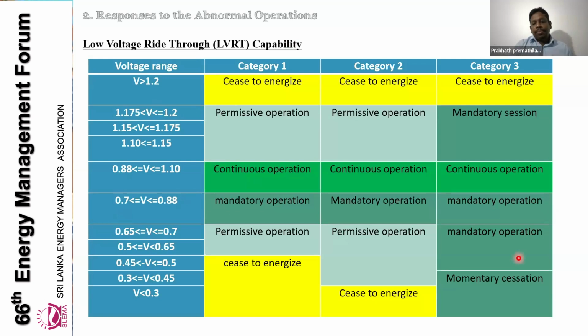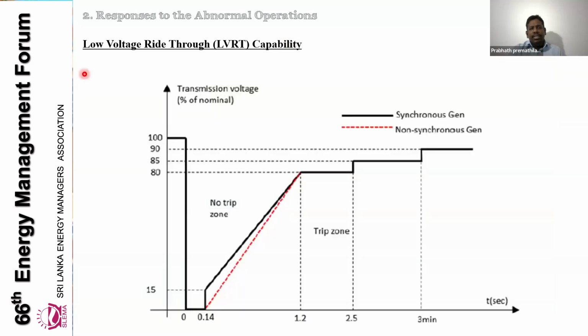So what happens? Let me explain with the LVRT curve we use in the grid connection code. If there is any kind of voltage disturbance, let's say around a 50% voltage dip, here is this value. Up to this time, maybe around 1 second or 0.8 second, the inverter will not trip.